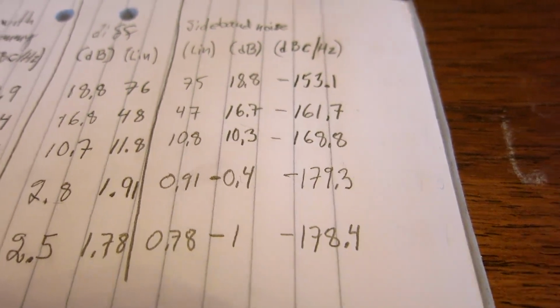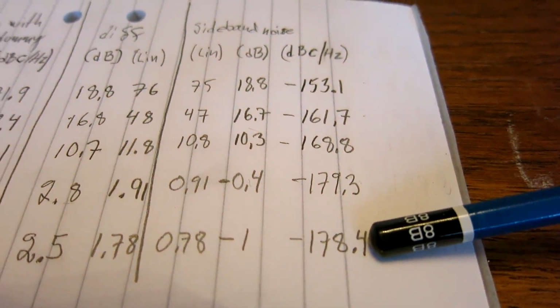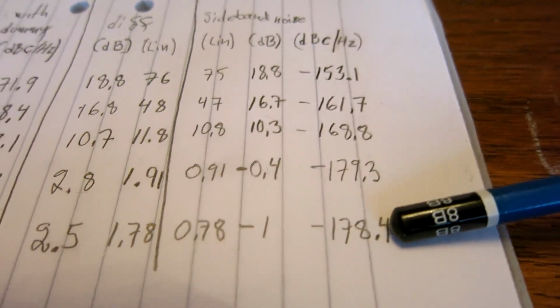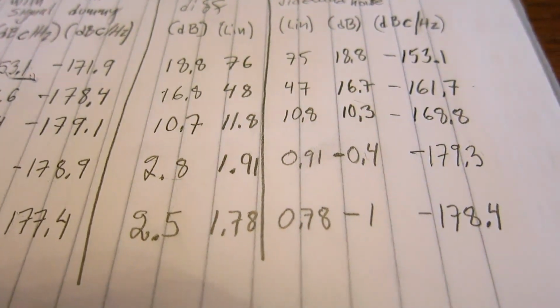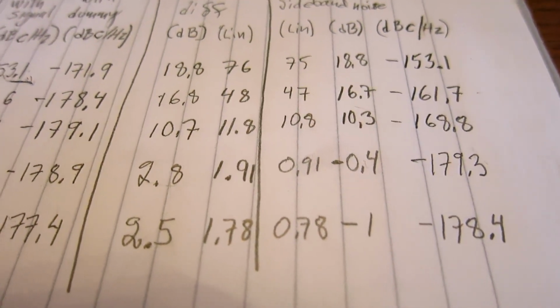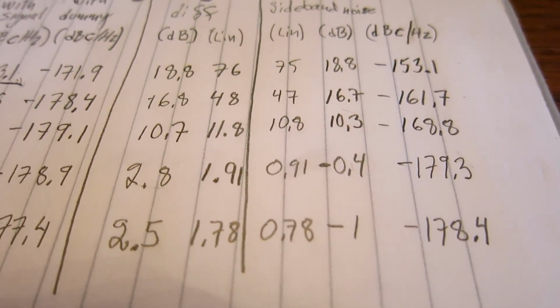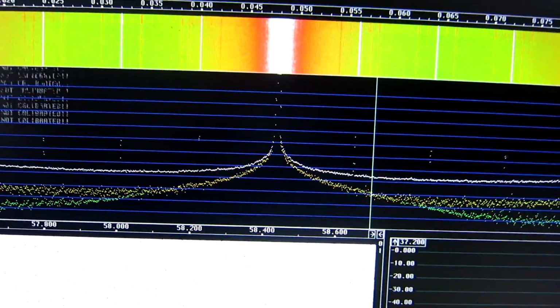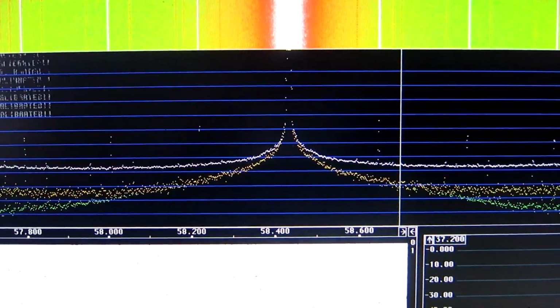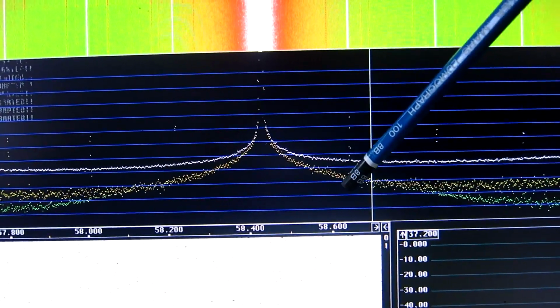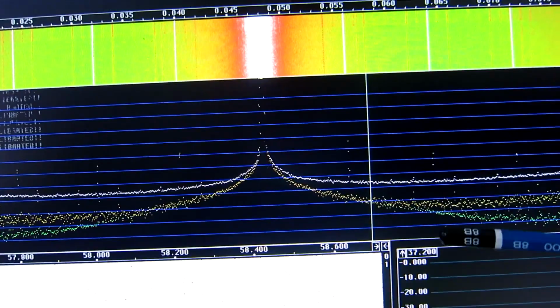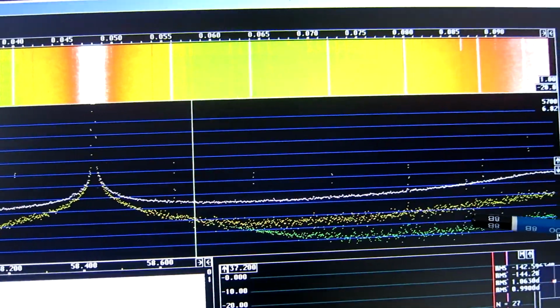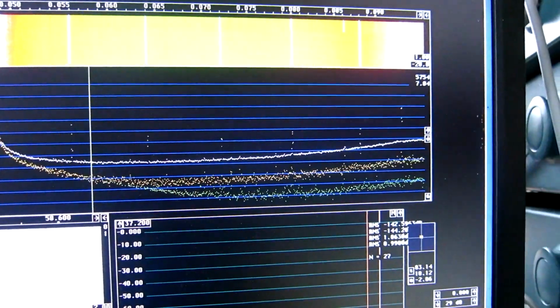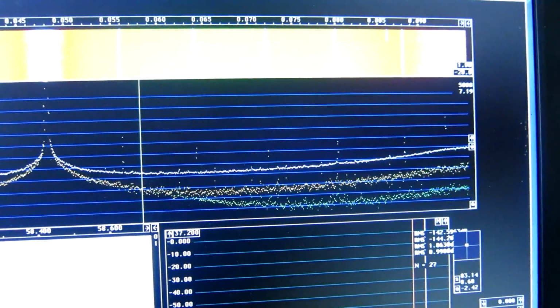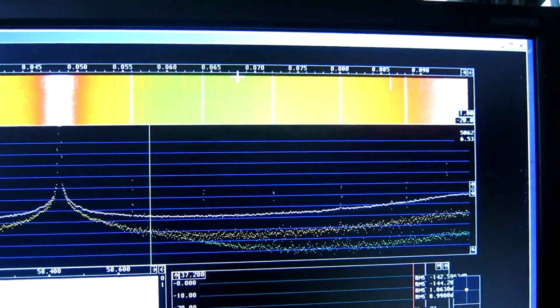So this should be what I'm looking at. And here maybe the sound card noise contributes a little bit more than I have evaluated. It's always difficult when the system noise is similar to the noise of the test object. Just looking at the screen here is quite clear. We can see that the oscillator noise dominates in this range. And here, when the noise goes up, it is probably the sound card that dominates. So a good measurement on the LO should be here.